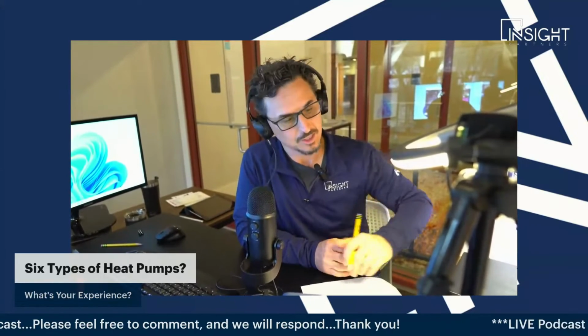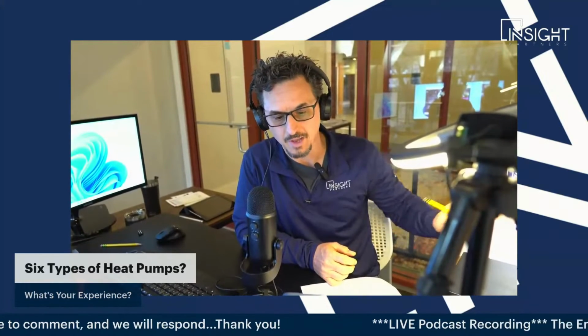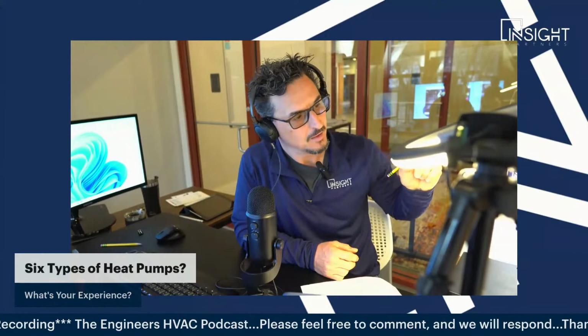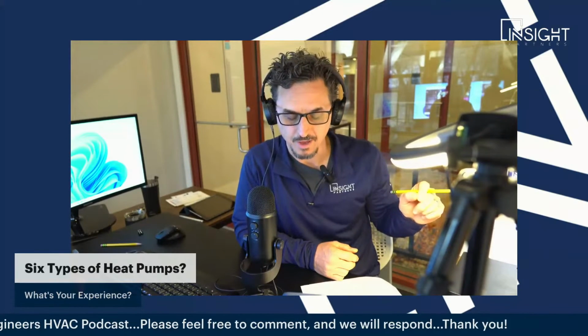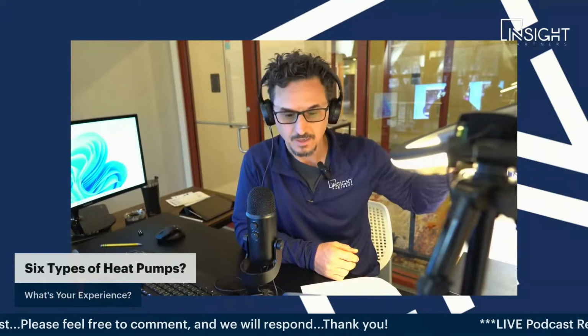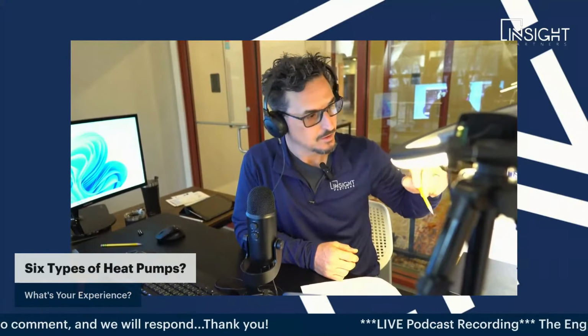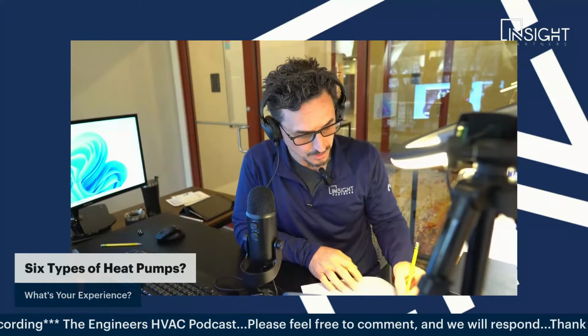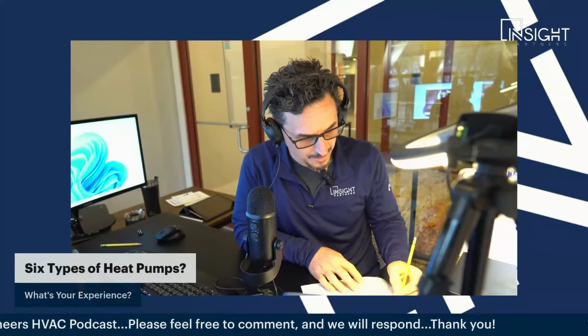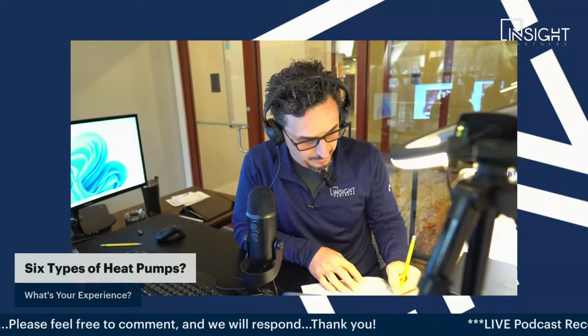So for water source heat pumps, let's say you'd have a cooling tower somewhere feeding a small water source heat pump, 3 to 5 ton, in each classroom, let's say if you had a school. You have this water loop and you're cooling it, taking the BTUs from there and putting it into your classroom through the refrigeration cycle. That's a water source heat pump - a little less common than the air source, but pretty common nonetheless.